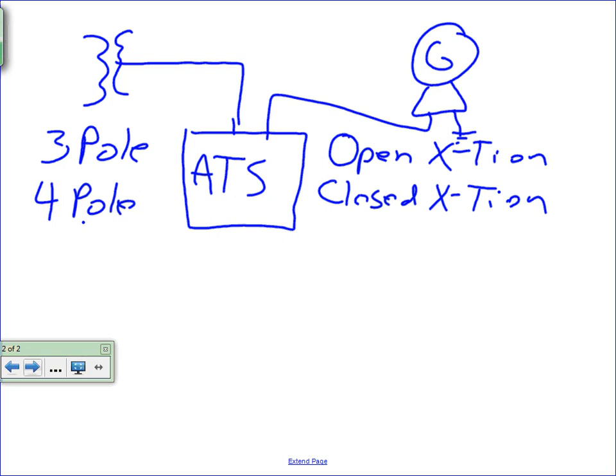So in that application, we would use a 4-pole device so that the neutral and phase currents are all switched back and forth to each source, okay? Now say that instead of a utility here, utilities upstream. Oh, what did I do? It's not writing them. We're feeding a main switchboard. We're bonding this at this location, right? Neutral to ground because it's the service entrance.